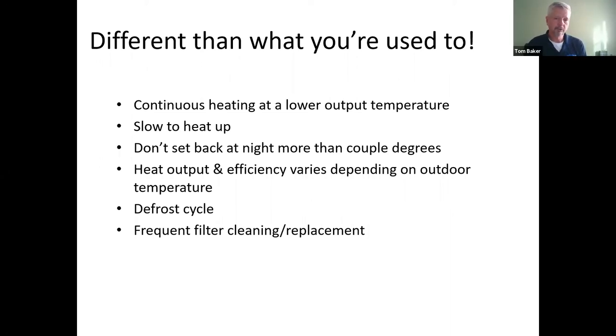One other thing I'll mention too. Well, I'm going to mention two other things. One is heat pumps, on occasion, will begin to ice up the coil. Again, you've got 20 degree refrigerant inside a copper tube. So there are certain circumstances where humidity plus temperature and other things may cause ice to begin developing. So the heat pumps all have a defrost mode. When that starts happening, it will kick off and revert to a defrost mode, defrost the coils, and then come back on and continue heating your house.